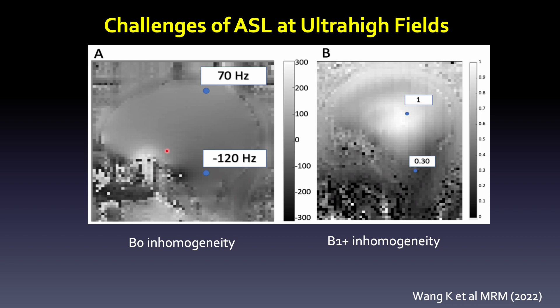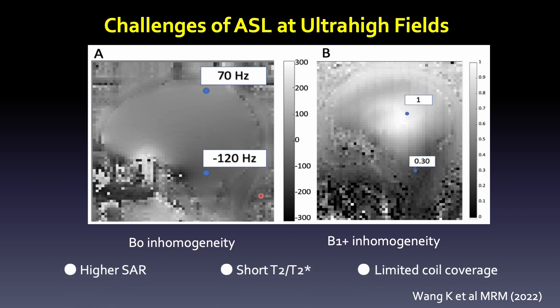However, the B0 and B1 inhomogeneity also increase at ultra-high field, as shown in this B0 field map. One ppm offset is about 300 hertz at 7T, and it's only 120 hertz at 3T. The B1 can decrease by 30 percent at the labeling region. On top of that, we have high SAR, shortened T2, T2 star, and limited coil coverage.